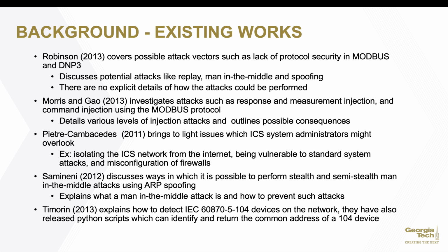I also want to introduce a little bit of the existing publications which are related to this paper. Much of the existing work is based on the Modbus and DNP3 protocols. In comparison, the 104 protocol is also vulnerable to many of the same kinds of attacks. A key vulnerability for most systems is the lack of authentication or validation mechanisms for data communicated via 104, and similar protocols such as DNP3.